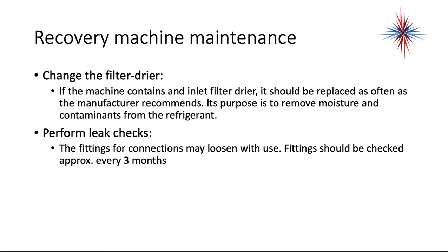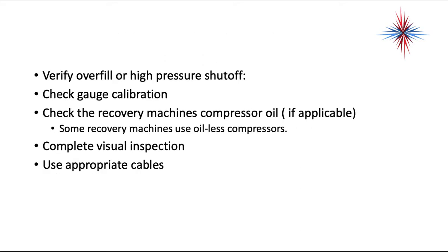So there's some maintenance that needs to be done on recovery machines occasionally. The filter dryer needs to be changed. If the machine contains an inlet filter dryer, it should be removed and replaced as often as the manufacturer recommends. Its purpose is to remove moisture and contaminants from the refrigerant. You need to perform leak checks occasionally. The fittings for connections may loosen with use. Fittings should be checked approximately every 3 months. You need to verify the overfill or high pressure shutoff, check the gauge calibration, and check the recovery machine's compressor oil if it has any. Some recovery machines use oil-less compressors. You want to do a complete visual inspection, and you want to use appropriate cables to connect the recovery machines to power.